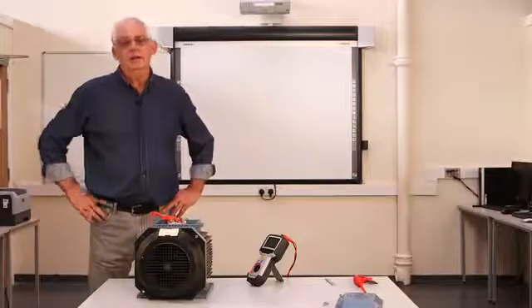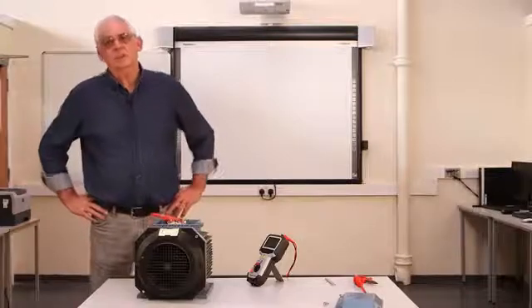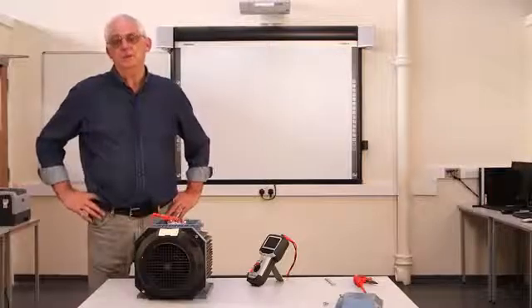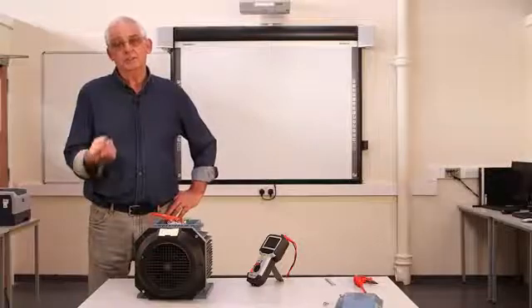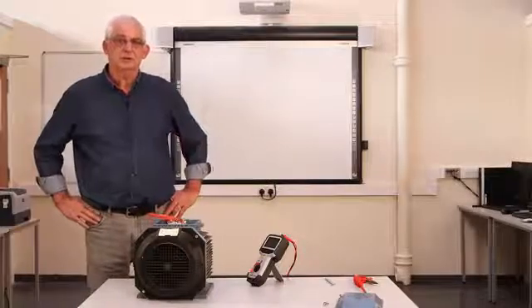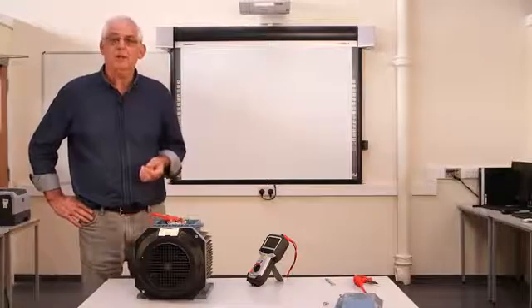And the value needs to come out greater than 2 means the motor's serviceable. If it's greater than 3 or even 4 or 5, it means the motor is in excellent condition. The windings, the varnish around the windings or whatever insulation there is, is in really good condition. So we'll just do a quick calculation on the board just to find out what the values actually are. And that's our polarization done.